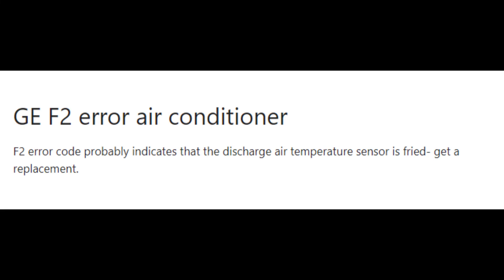Error code F2 means the discharge air temperature sensor is bad. If you see this error code, you need to change the discharge air temperature sensor on your GE air conditioner.